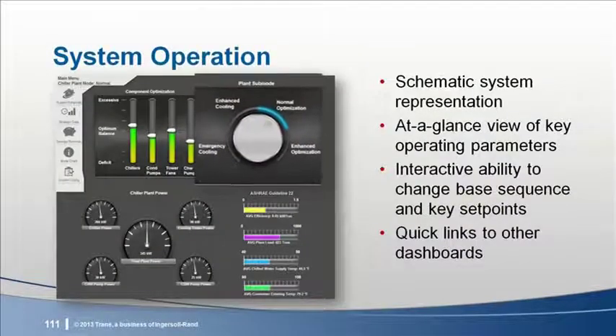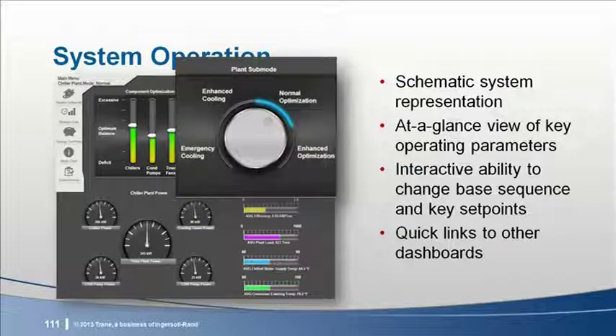A concept to alleviate this manual override response is the addition of a system mode selector. Such a selector would allow an operator with proper authority to change the system operating sequence from full optimization to enhanced cooling or emergency cooling for a set override period of time. The two override modes reduce and eliminate the optimization resets respectively to ensure the maximum flow of the coolest chilled water possible is available to the building.